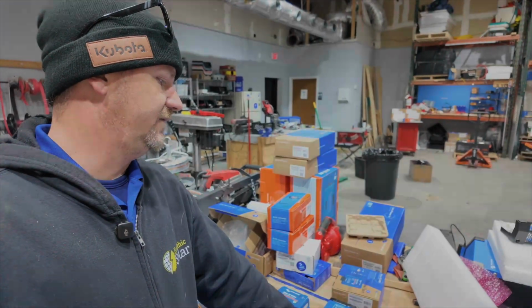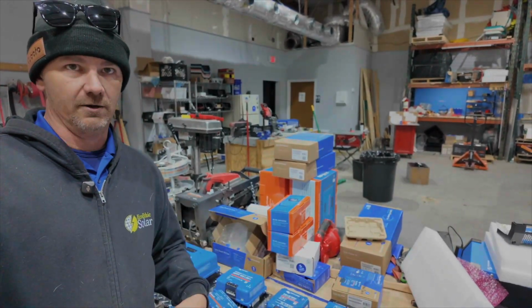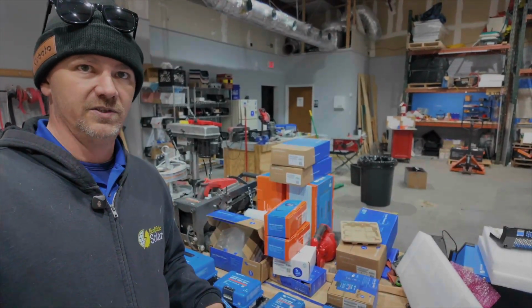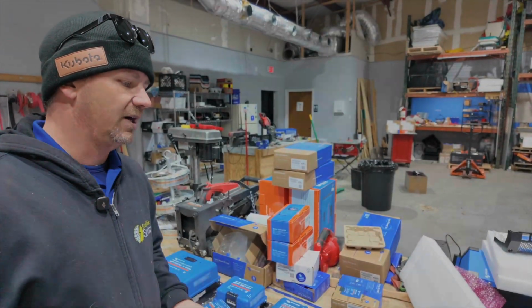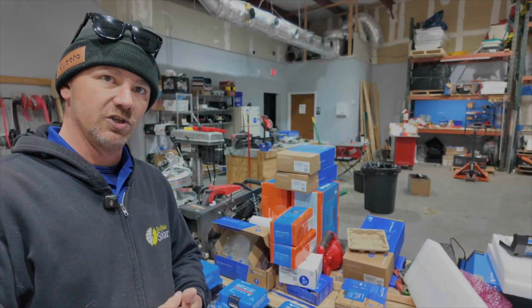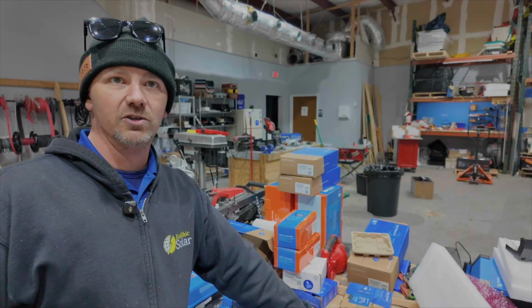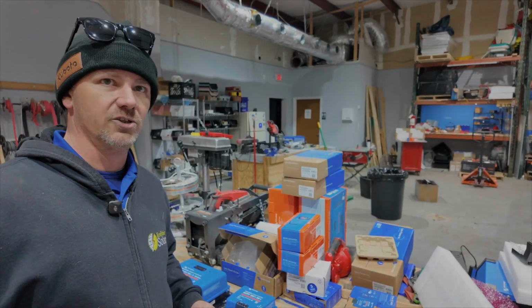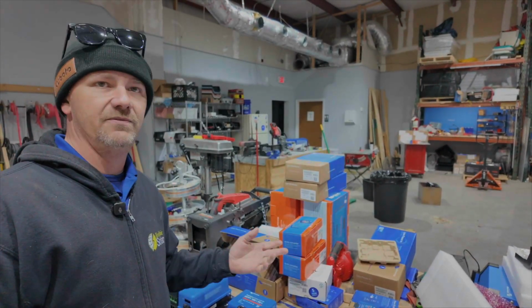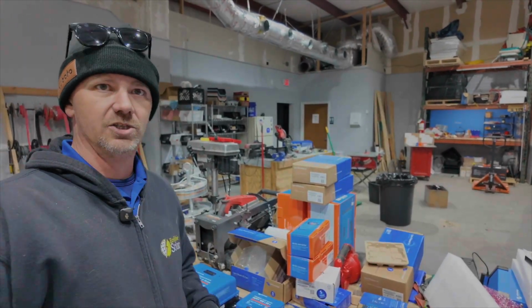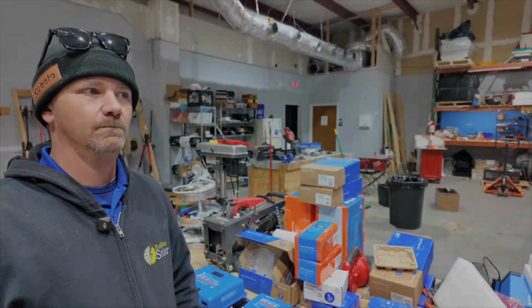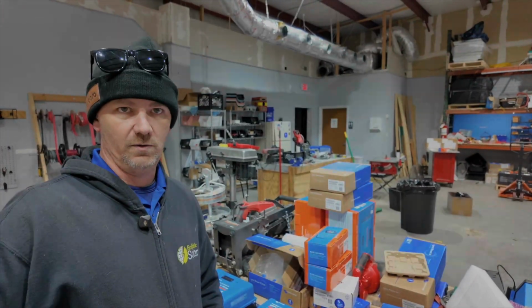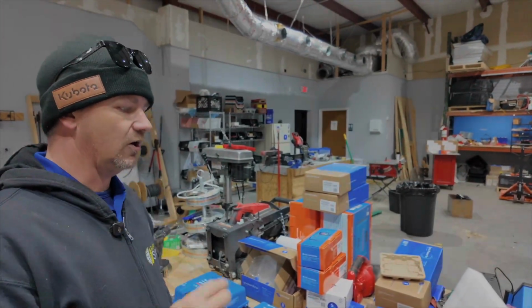The outputs of these go to a buffer battery and then on to your house systems. We put the buffer battery in so that if you have large surge loads these can't supply, the battery can give you that extra oomph, an extra 50 to 100 amps of surge, like the inrush on your jacks or the generator's starting circuit.